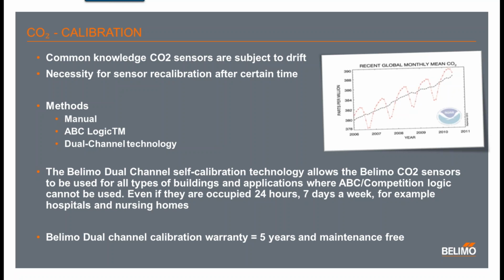The Belimo dual channel self-calibration technology allows the Belimo CO2 sensors to be used for all types of buildings and applications where ABC logic and competition logic cannot be used, even if they're occupied 24 hours a day, 7 days a week, such as hospitals and nursing homes. The Belimo dual channel calibration warranty is guaranteed for 5 years and is totally maintenance free.